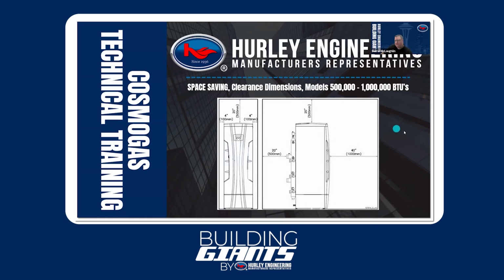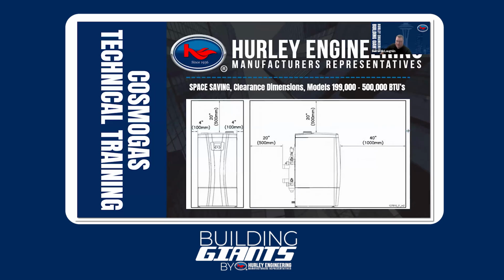And that holds true whether it's the large version. So this would be our large, either 750 or 1,000,000 BTU model, and it's the taller of the two. And if we go to the smaller one, that would be either 250 or 500. It has the same clearances, so nothing changes there. 4 inches to combustibles, 20 or 40 inches clearance for service and access, with no change between the models.